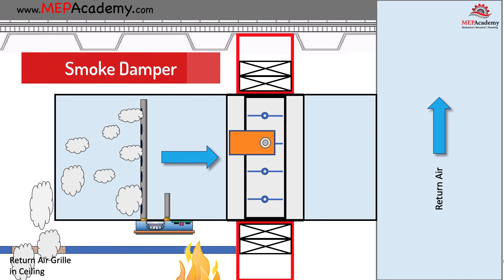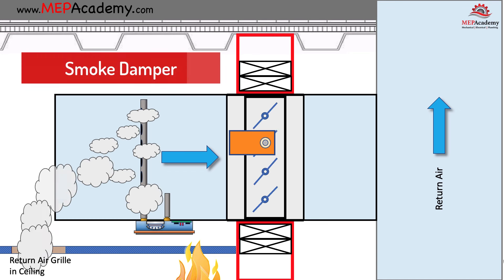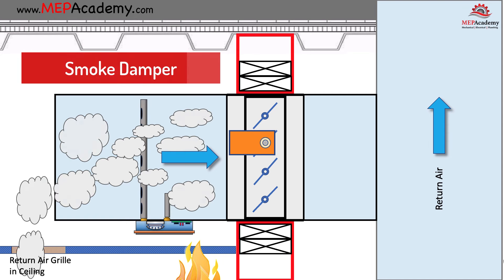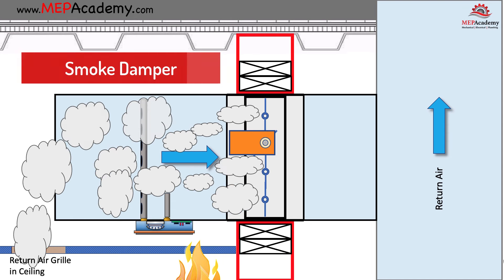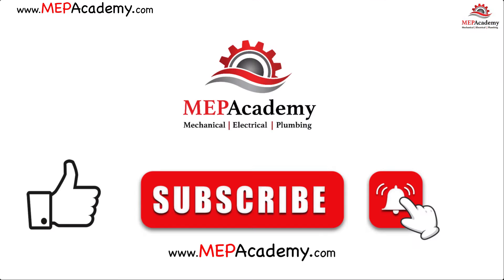There are also fire smoke damper combinations that protect the opening using both techniques. According to the NFPA, a combination fire smoke damper is used when a barrier is both rated for fire resistance as well as designed to restrict the transfer of smoke, and will meet both the fire damper and smoke damper requirements.